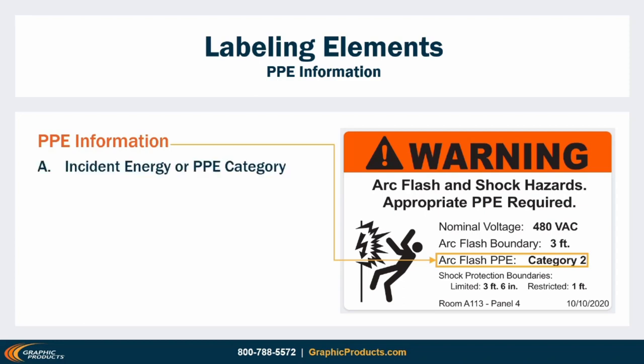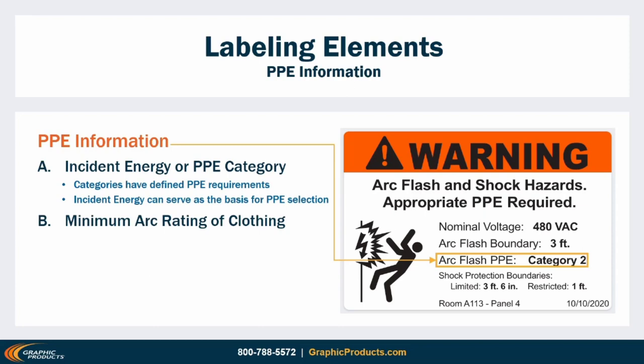The third requirement — at least one of the following — is a collection of ways to answer what PPE is needed. Option A is the most direct: if you used the PPE categories shortcut, you can show the PPE category for this equipment; if you calculated an incident energy value, you show that incident energy and the working distance it's based on. You won't use both options at the same time, and trying to show both on the same label is not allowed. Option B, the minimum arc rating, is a more user-oriented way to give PPE information. The arc rating of PPE indicates the maximum heat energy in cal/cm² that it can safely block or absorb, and all arc-rated PPE will be clearly marked with its arc rating number. This allows workers to compare the number on the label to the numbers on their gear.